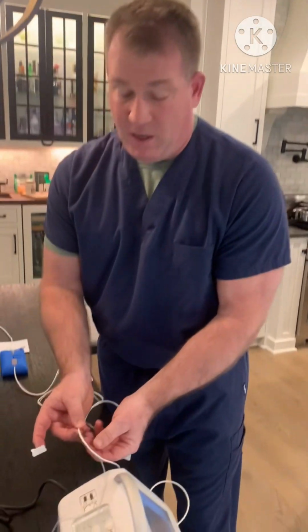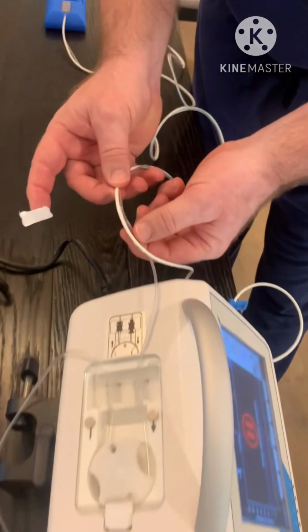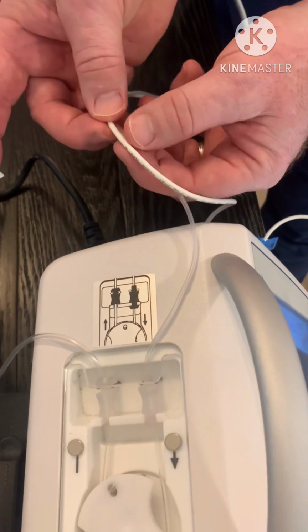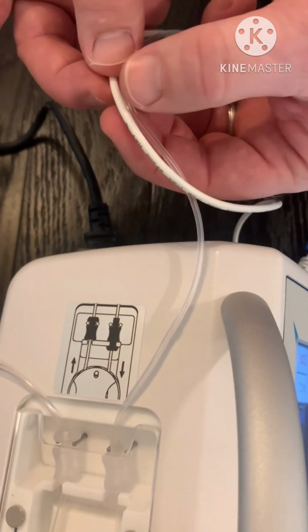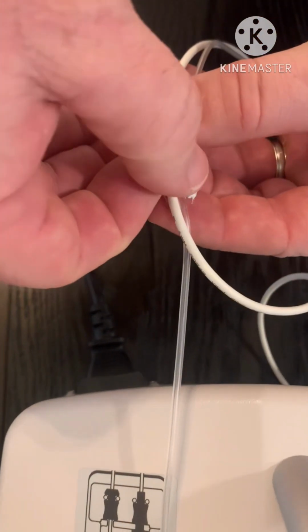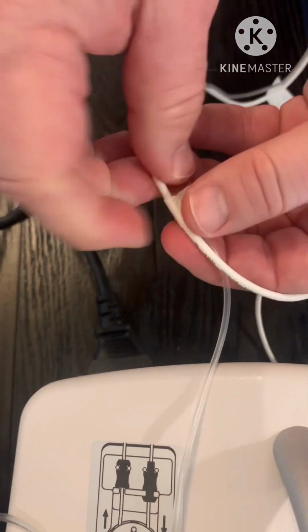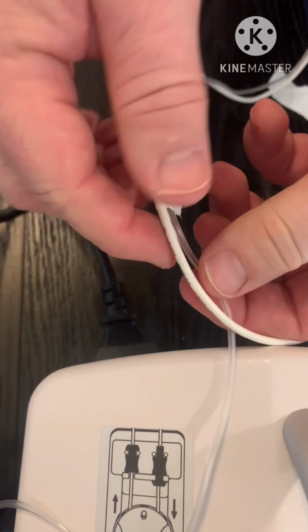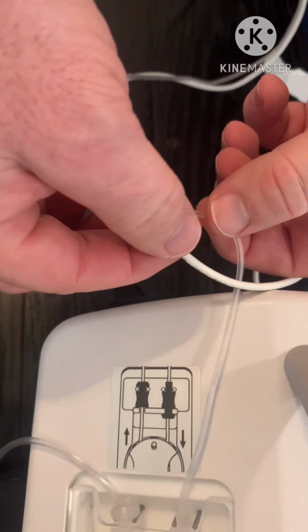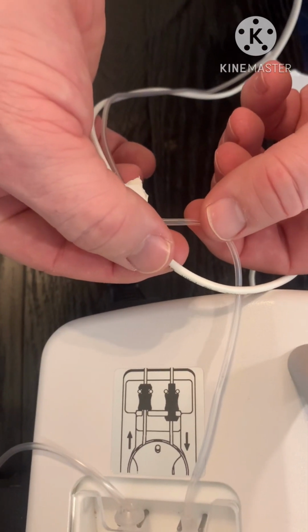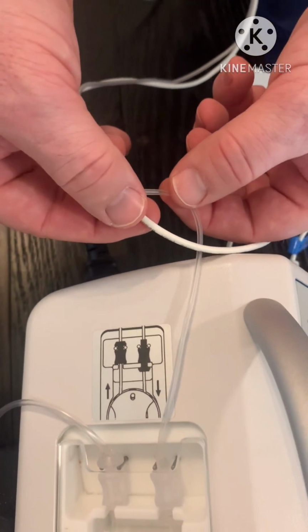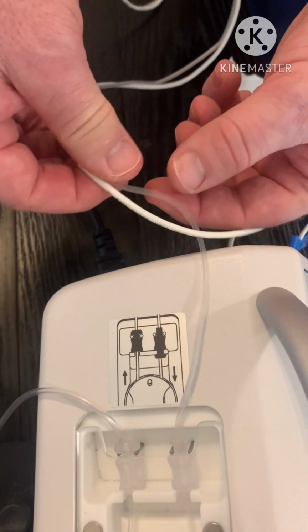Last step. Go to your tube set where it enters the rotor and find this first glue point where the tube is glued to the white cable. Put a thin, small piece of tape around that. That discourages anybody upstairs or anybody at all from peeling this away like it's a piece of licorice. Peeling that away will create a micro tear, so we want to discourage that.